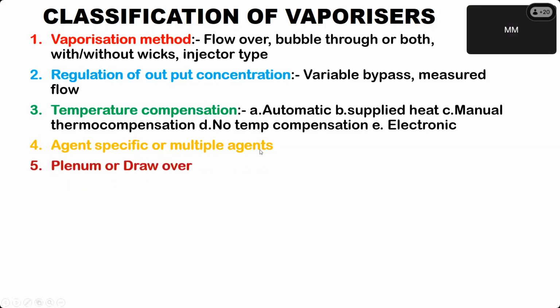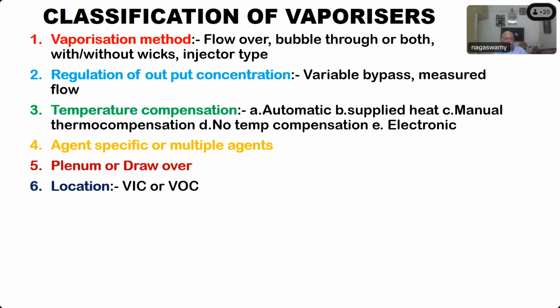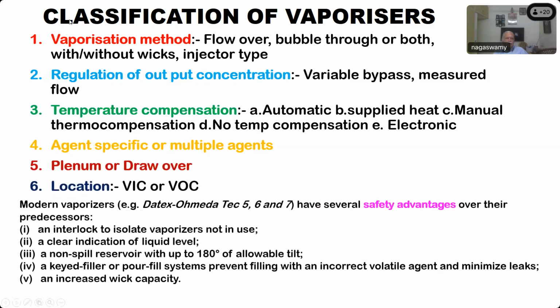You are very well versed with the latest developments rather than the history. Okay. Plenum or draw over vaporizer, and it can be inside the circuit or outside the circuit. Vaporizer inside the circuit and outside the circuit. So these are all the 6 classifications: vaporization method, regulation of concentration, temperature compensation, whether agent specific or multiple agents, or plenum or draw over, location, whether within the circuit or outside the circuit.